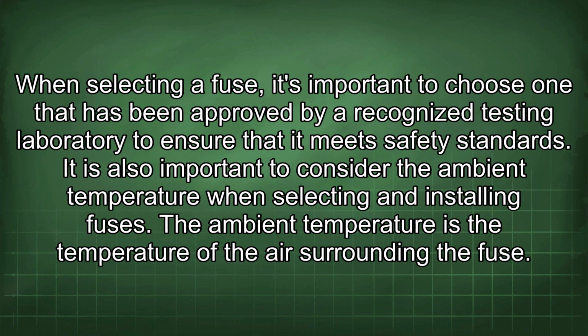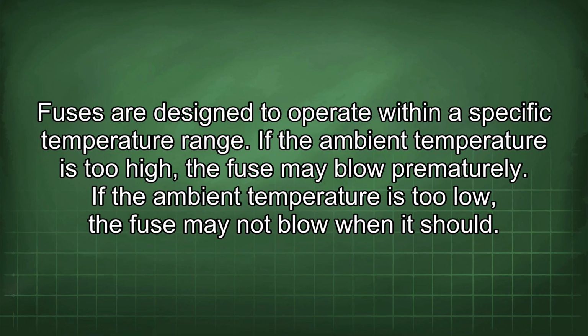When selecting a fuse, it's important to choose one that has been approved by a recognized testing laboratory to ensure that it meets safety standards. It is also important to consider the ambient temperature when selecting and installing fuses. The ambient temperature is the temperature of the air surrounding the fuse. Fuses are designed to operate within a specific temperature range. If the ambient temperature is too high, the fuse may blow prematurely. If the ambient temperature is too low, the fuse may not blow when it should.